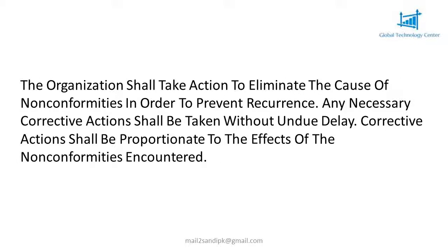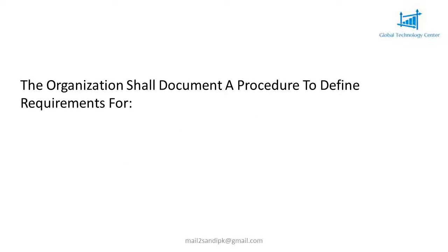The organization shall take action to eliminate the cause of nonconformities in order to prevent recurrence. Any necessary corrective actions shall be taken without undue delay. Corrective actions shall be proportionate to the effects of the nonconformities encountered. The organization shall document a procedure to define requirements for A.